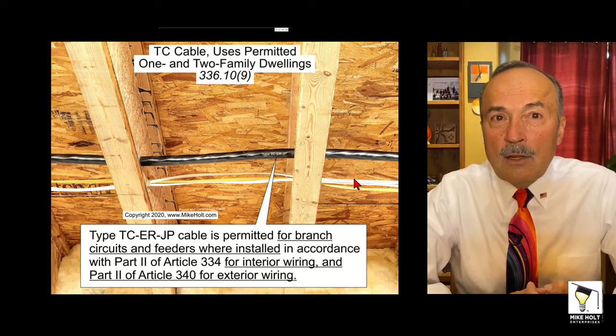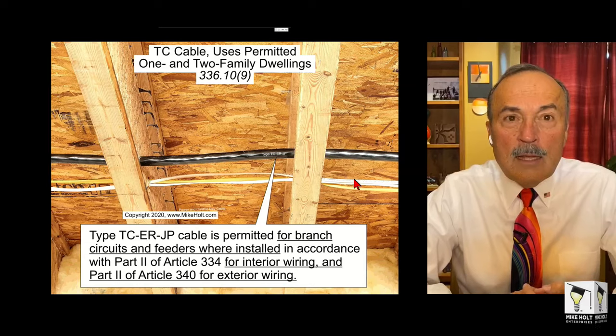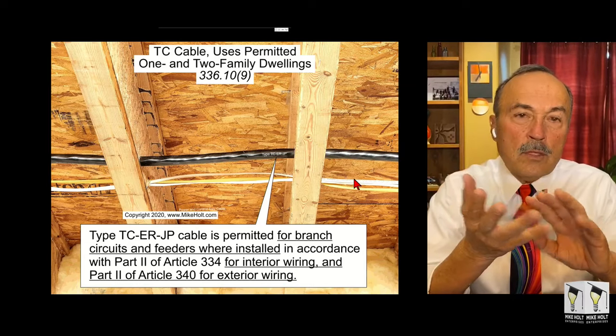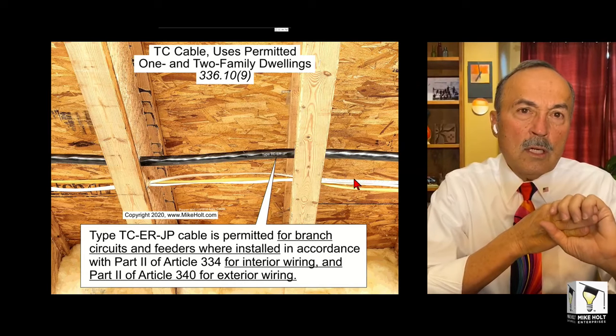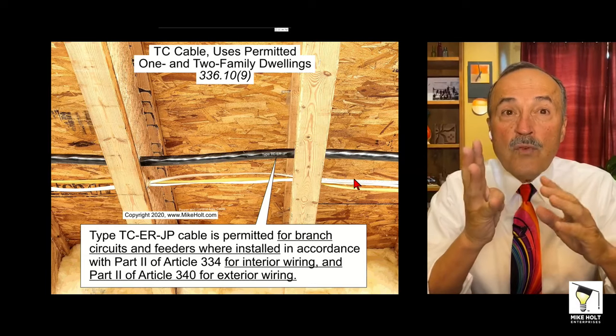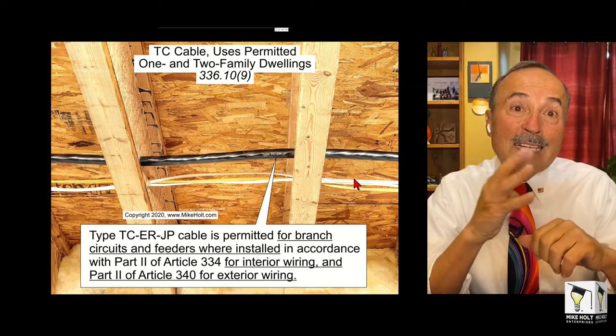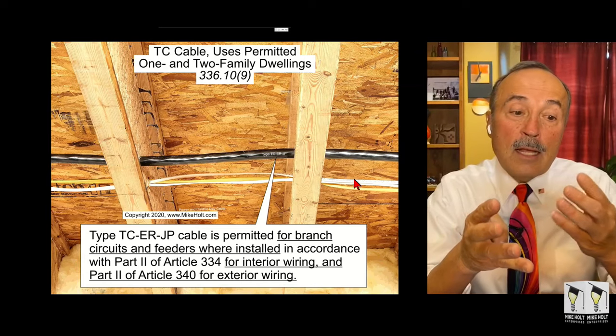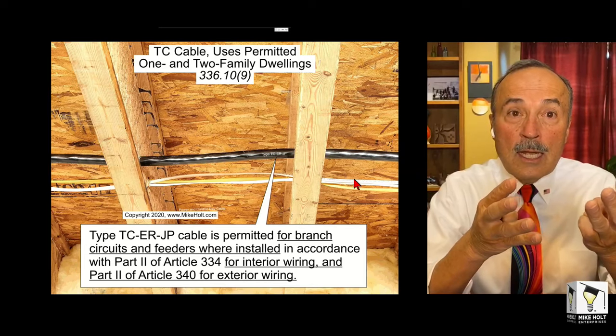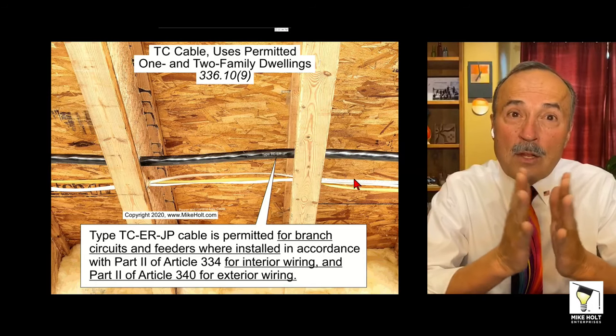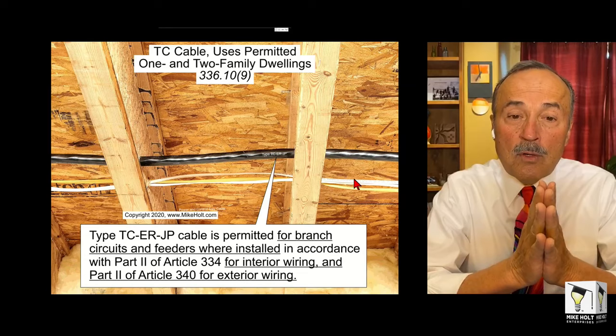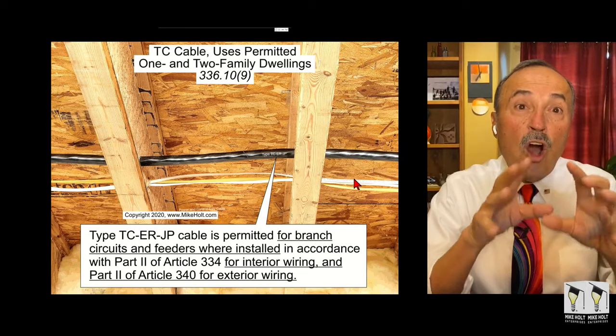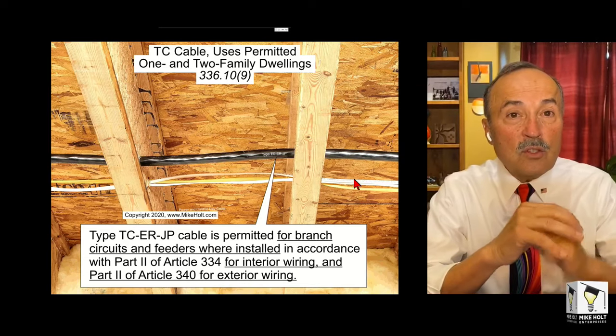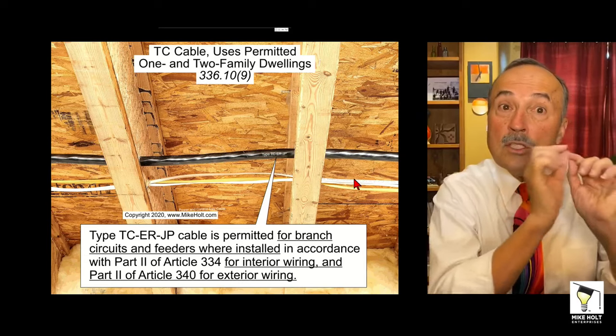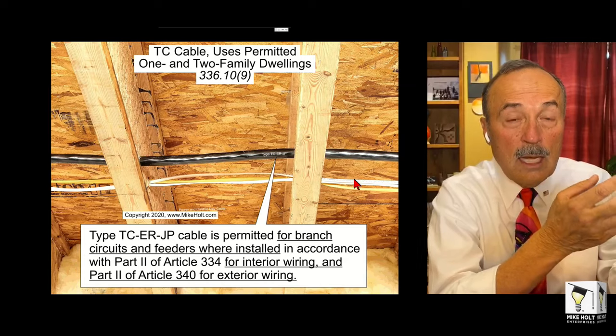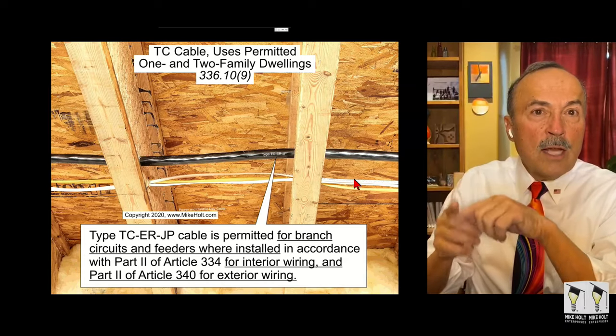All right, so what Generac did, and they're a fantastic company, other than I don't like that instruction, they came out with a tray cable that had the two hots, the neutral, and, Brian, what is it, four control conductors inside that control the Generac? So there are four control conductors, and those control conductors are Class 1 and 600 volt rated, and they ran 600 volt rated phase and neutral conductors. They put it within the same jacket. So they made a brand new product with type TC tray cable that included the phase conductors, the neutral conductors, and their control conductors, in all the colors that they want. So when you get to your transfer switch, you bring the tray cable into the transfer switch equipment and you just terminate it according to the colors, right? Doesn't take a lot of intelligence there. It's not like hooking up a thermostat where you're all confused. And then you go over to the generator and you do the same thing at the generator.